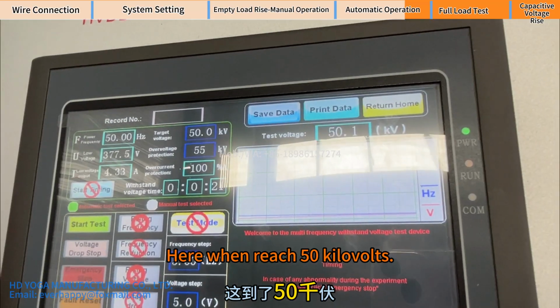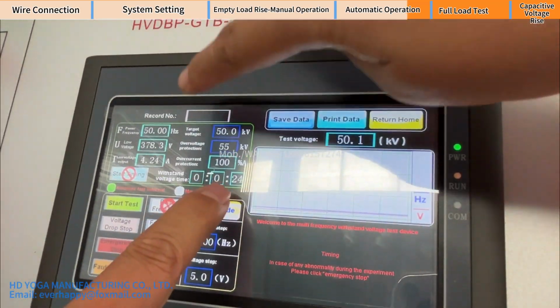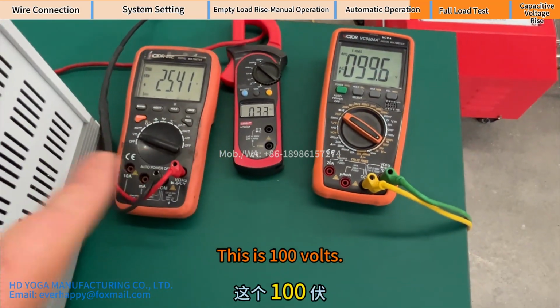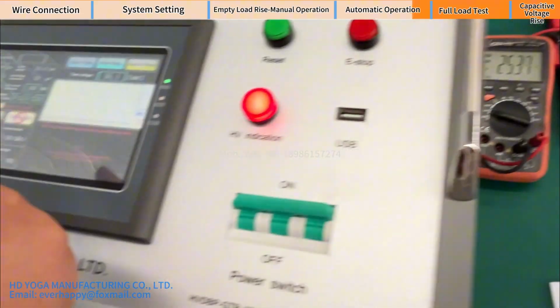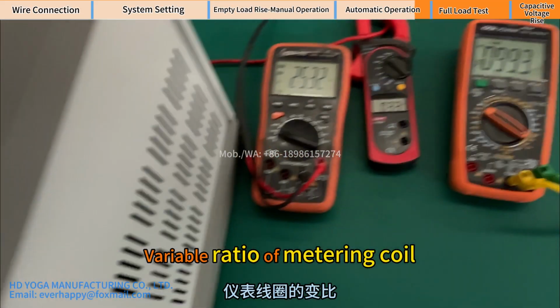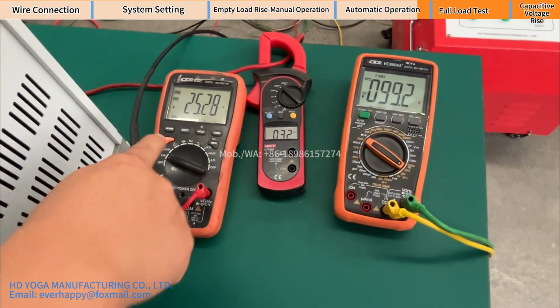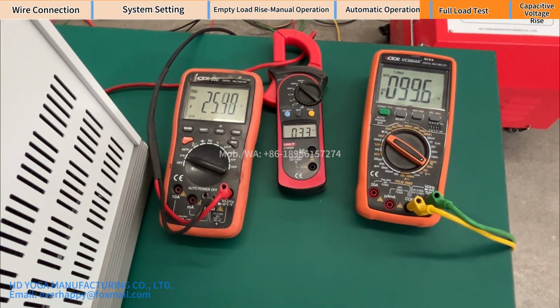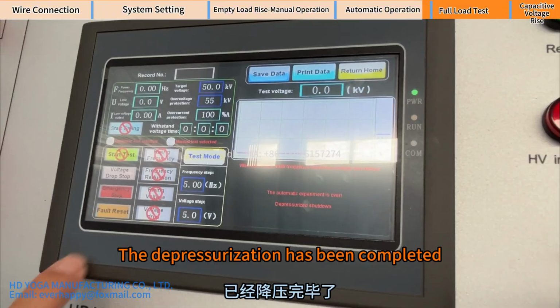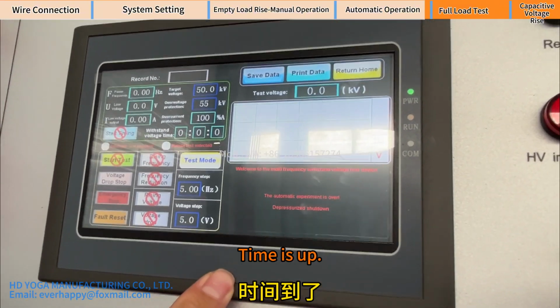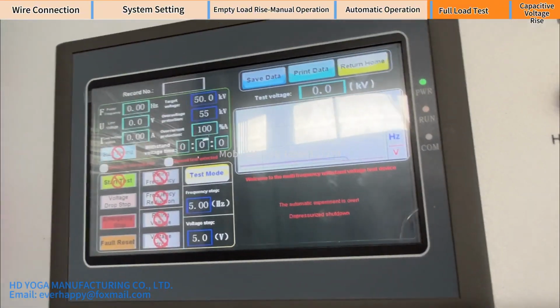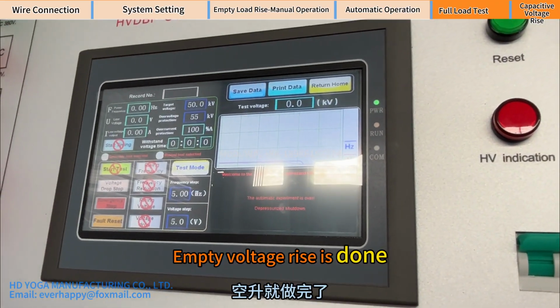Here, when it reaches 50 kilovolts, it starts timing automatically. This is 100 volts. That corresponds to 50 kilovolts. The variable ratio of the metering coil is definitely no problem. This is within the margin of error. That's 1% error. The depressurization has been completed. Time is up. The timer is usually set to 1 minute. The empty voltage rise is done.